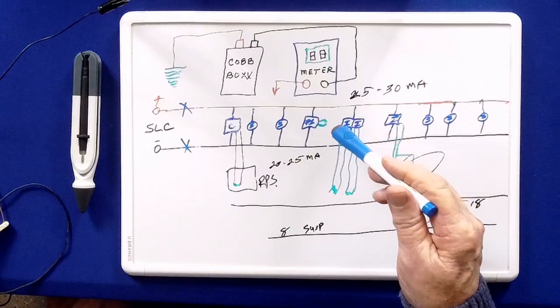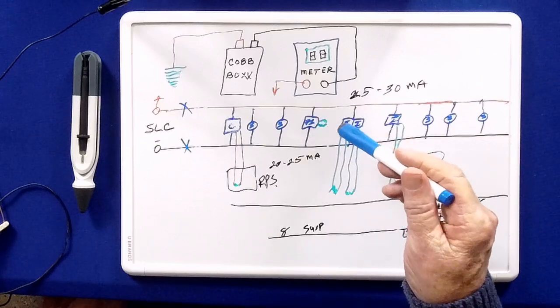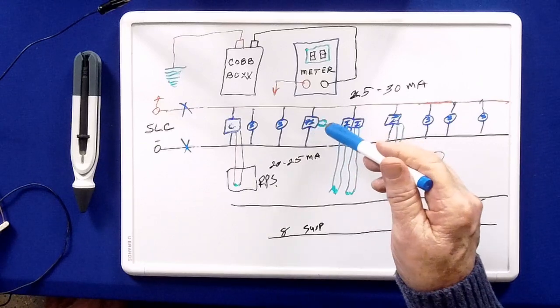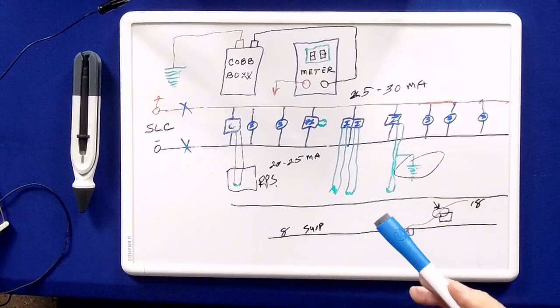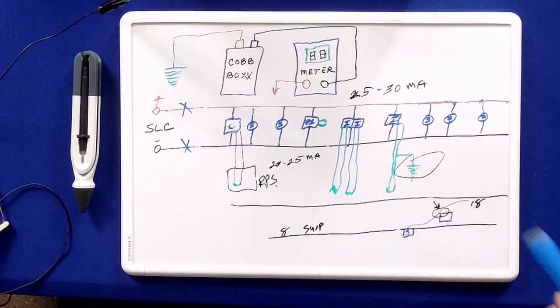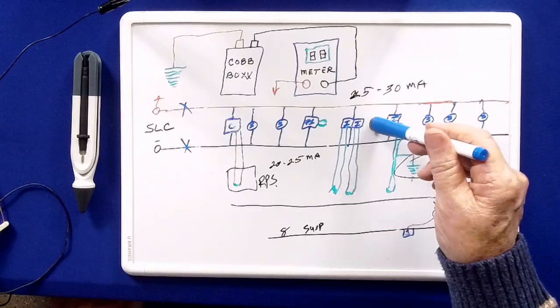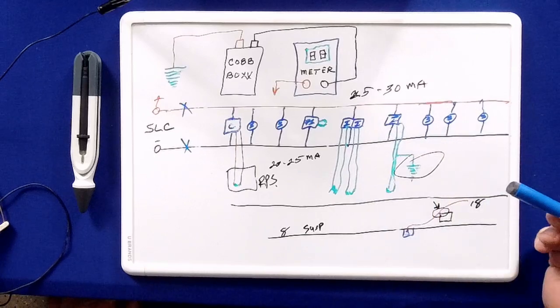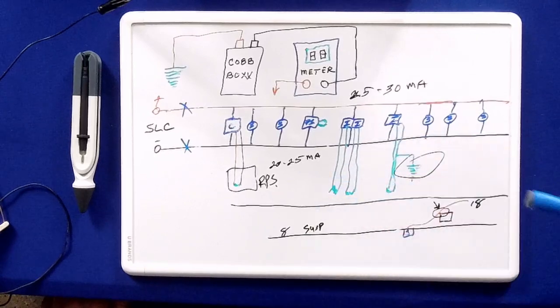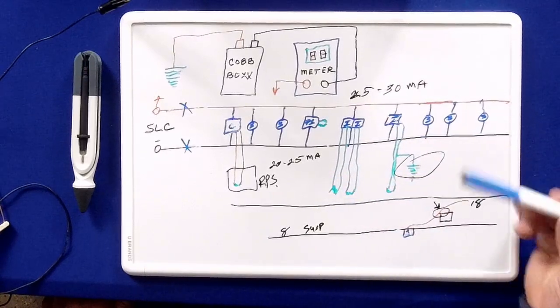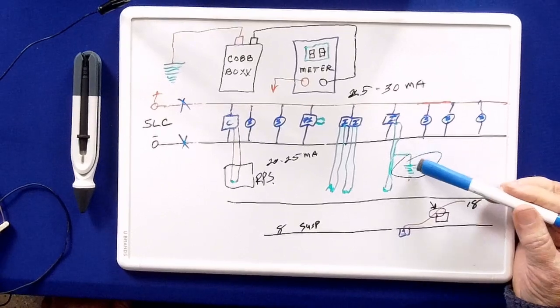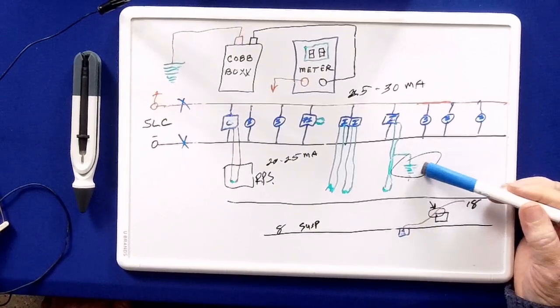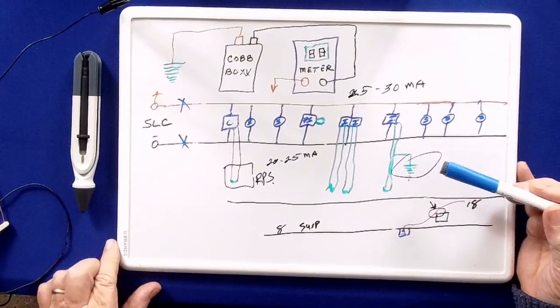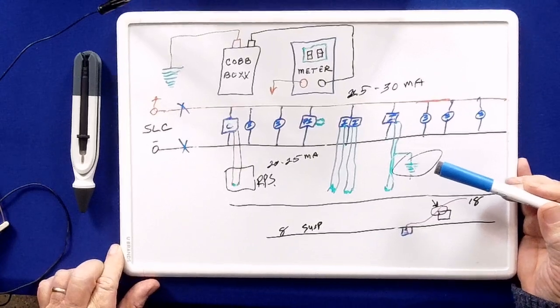A pull station. Most of them these days are plastic, and it's a very short circuit in there. They got many modules in there that work that pull station. However, now we get to a double module and a single module, initiating circuits. They go out in the field with Class B circuits.